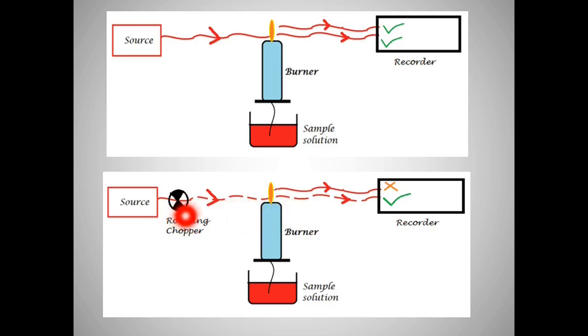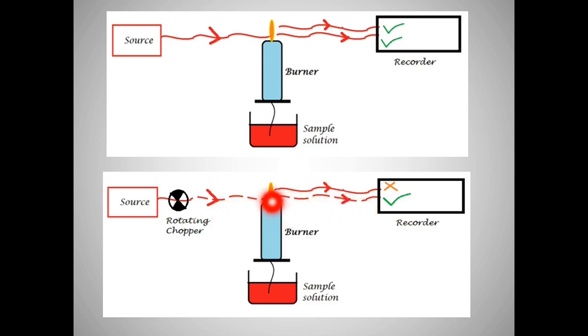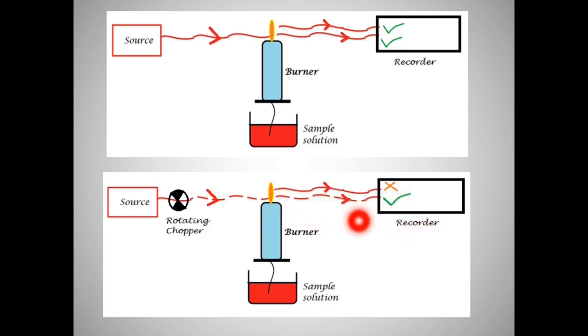Since the light from the source is present in an alternating form after being chopped, while the light emitted by the flame is not chopped and is not alternating, we can set the recorder to read only the alternating current. In this manner, the rotating chopper helps the recorder distinguish between the two light radiations.